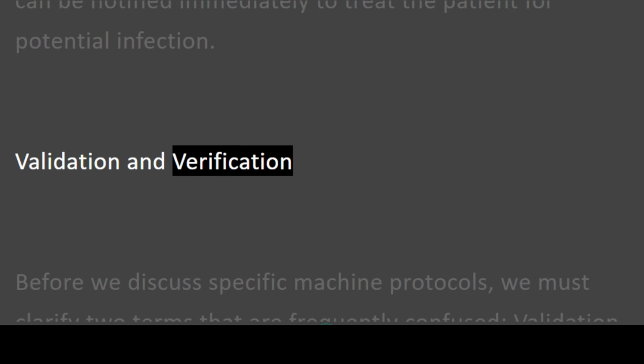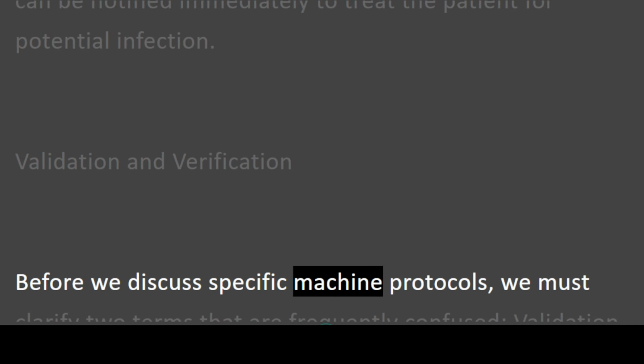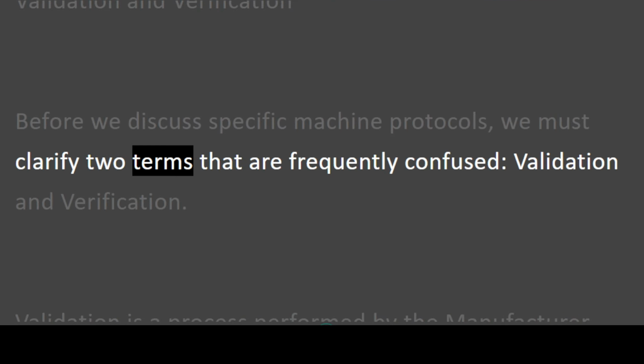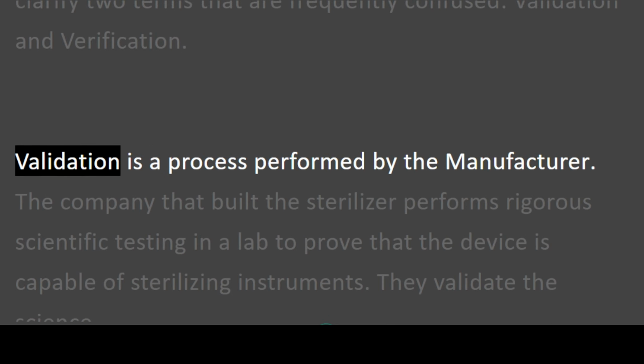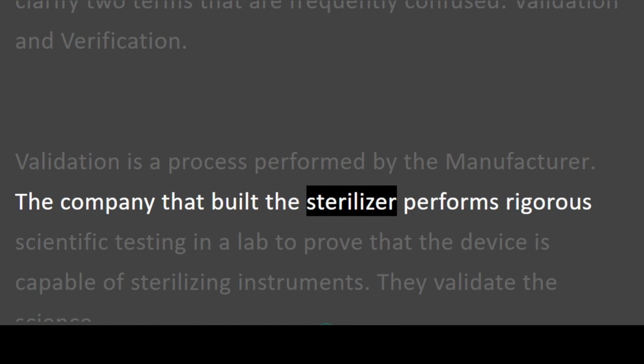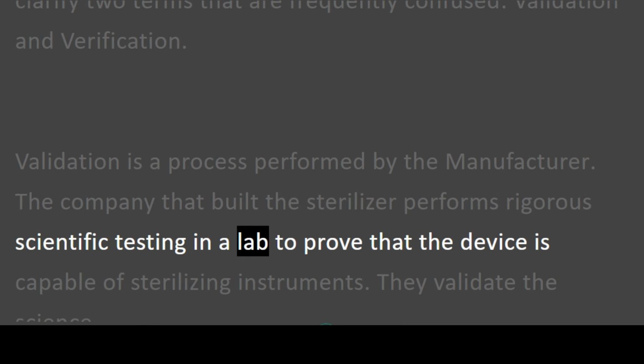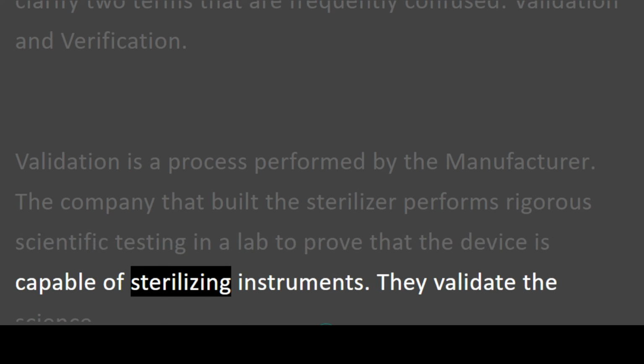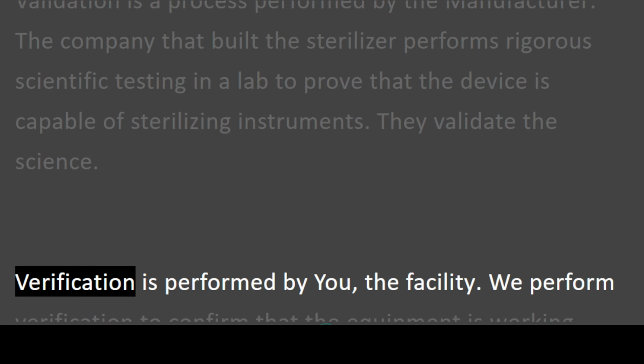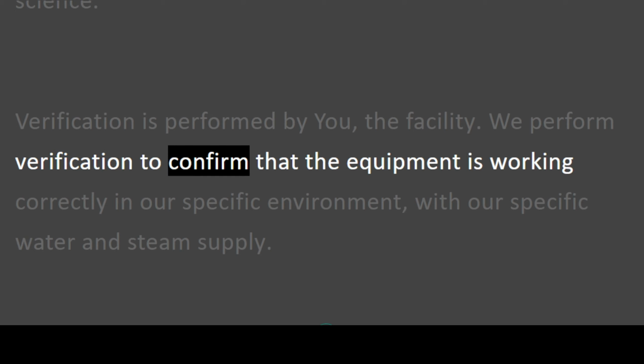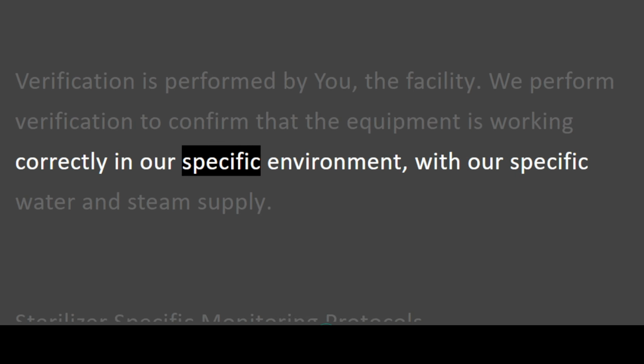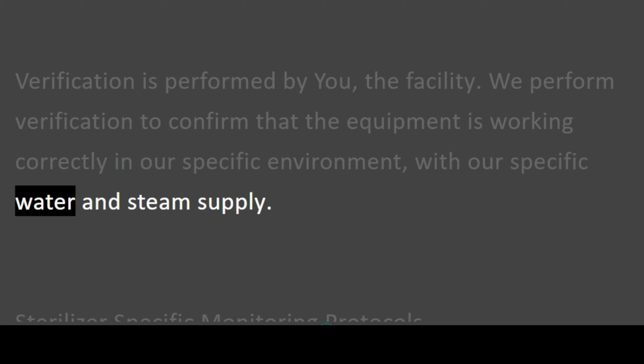Validation and verification. Before we discuss specific machine protocols, we must clarify two terms that are frequently confused: validation and verification. Validation is a process performed by the manufacturer. The company that built the sterilizer performs rigorous scientific testing in a lab to prove that the device is capable of sterilizing instruments. They validate the science. Verification is performed by you, the facility. We perform verification to confirm that the equipment is working correctly in our specific environment, with our specific water and steam supply.